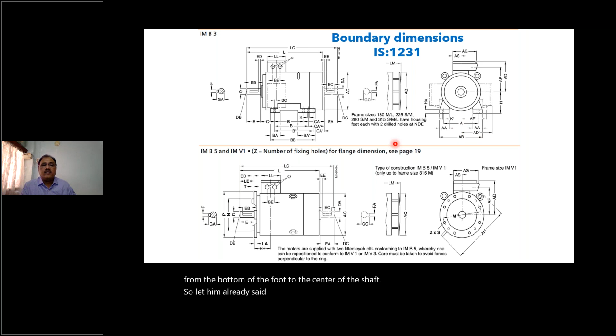Similarly, in the case of flange mounted motors, IS 2223, you will find mention of M, N, P. So you have N here, you have P here, and you have M for medium. M is the center to center of the flange holes. N is a step in the flange. This flange has to mate with the female flange. If it does not mate accurately, then the flange cannot be mounted. So for mounting a flange, you will have another flange from the machine side. So this N dimension has to match.